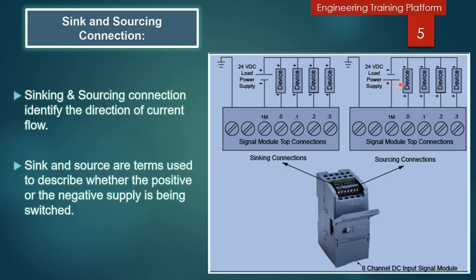For the sourcing connection, with the same 24 volt DC load power supply, the current flow direction changes. One side of the device is connected with the negative supply, and the other side of the device — the positive — is connected to the module. From the load power supply, the positive is connected to the module. This is known as the sourcing connection. There is no need to be confused, because at the time of connection it is mentioned in the specification whether the PLC requires sinking or sourcing connection.